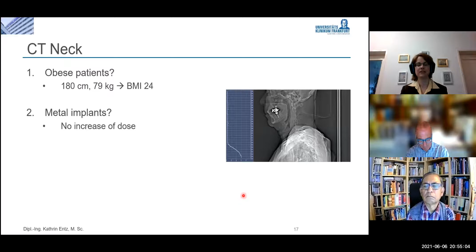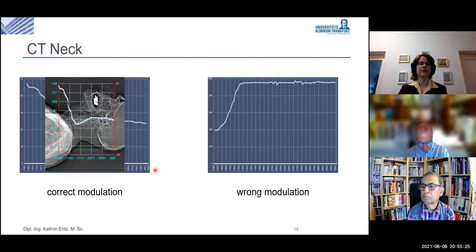The correct dose modulation, or tube current modulation, would be something like you have here on the left. In this area you would have the shoulders of the patient, then here the actual neck, and here the head area. So something like this. And for the patients where the doses were so high, you have a modulation like this. So it's actually the other way around. In the shoulder area you start with the lowest doses, and then it increases when you come to the head. So you know something is wrong with your dose modulation simply by looking at those dose values.